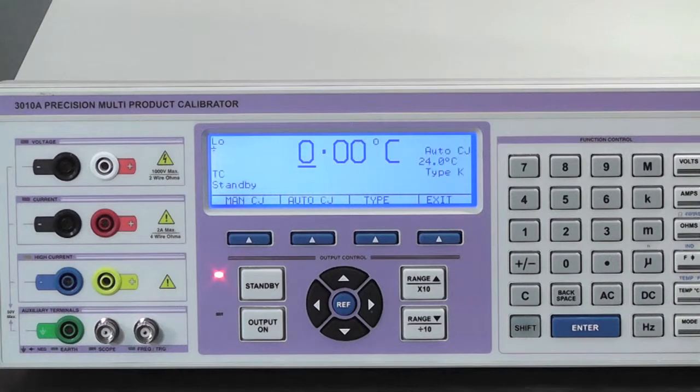To achieve the best accuracy when working with thermocouple calibrations allow all equipment to thermally stabilize. The displayed CJC temperature will help confirm when a stable environment has been achieved.